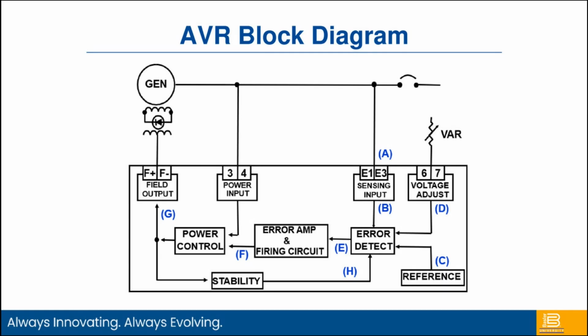A gets basically stepped down to a lower voltage signal within circuitry, and that's here at B, and it goes into this error detection scheme, and it compares this level against our reference set point. So this is going to be our base set point. Let's just say this was a 480 volt machine, we would have the set point set at 480 volts. But if our user wanted to make minor adjustments, we could also have this external adjustment, or this voltage adjust at D. In this case, it's a variable resistor. It could be a DC offset signal from another device, but it's a way to adjust the set point overall.